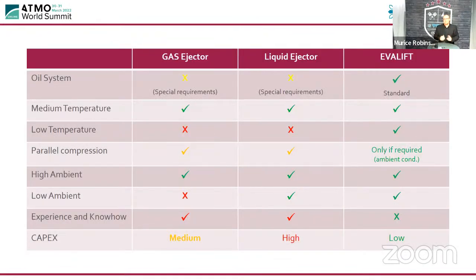Right, so I just want to compare some items with regards to EVALIFT, and just to explain the simplicity. And please don't get me wrong, gas ejectors and liquid ejectors, we install both, we manufacture for both. They do work. I'm not saying that they don't work. They're very good technology. However, they can be a little bit complicated when it comes to, for instance, the oil system. You need special designs and special installation pieces for the actual oil system when you're using a gas ejector or a liquid ejector, whereas with EVALIFT, it's a standard oil system, so any mechanic would actually know how to use it.